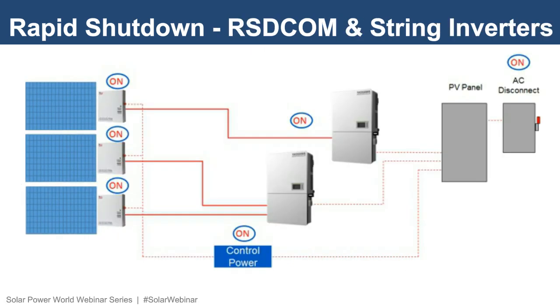This diagram highlights the use of Solectria TL string inverters coupled with Solectria's rapid shutdown combiners in a code-compliant installation. In this example, we have a PV system that is segmented into 3 array sections. This is often the case with larger commercial and industrial rooftop PV projects. A rapid shutdown combiner would be installed within the NEC-defined boundary of each array section.